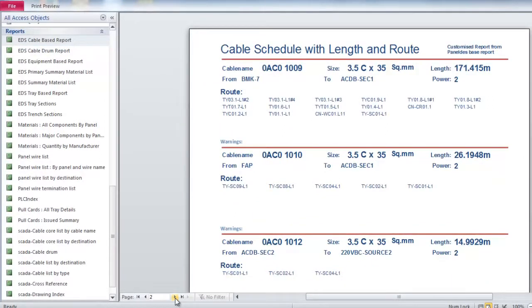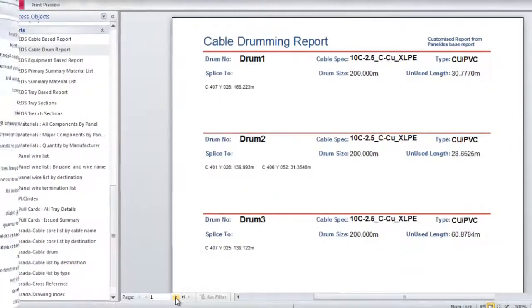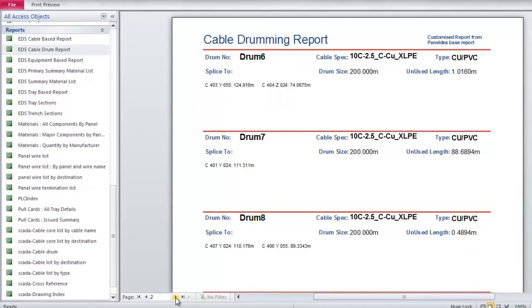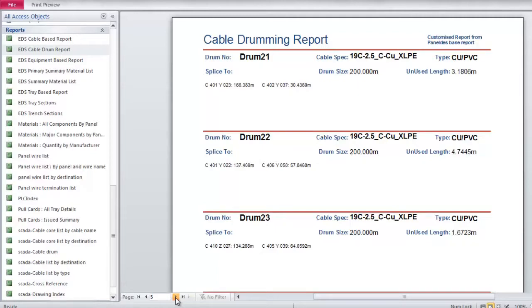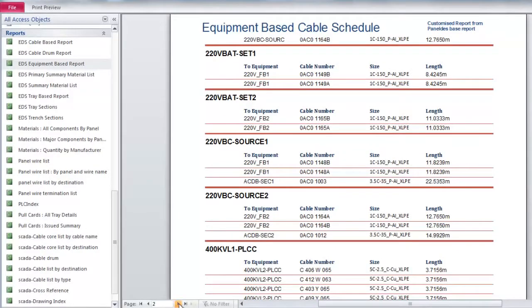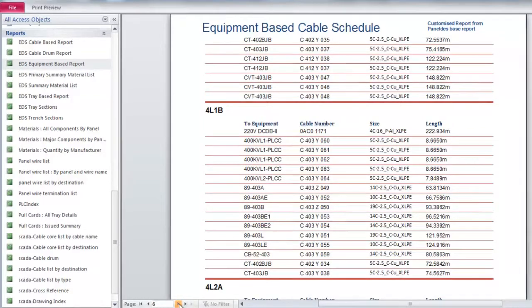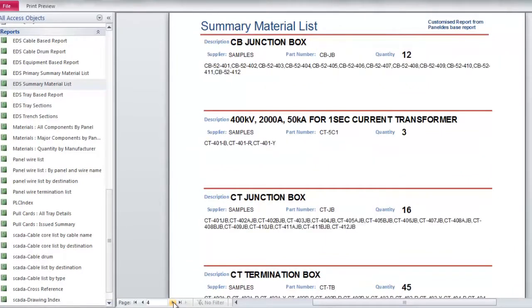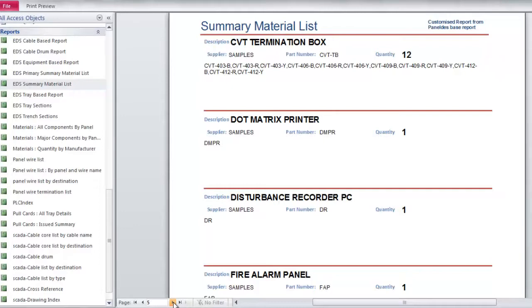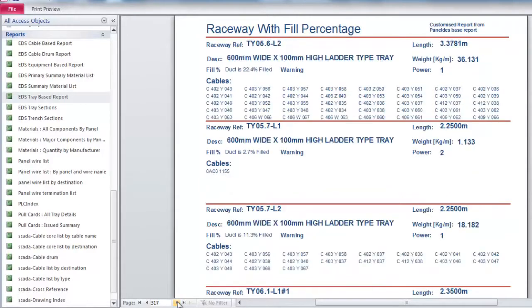PanelDes provides options for reports, including unformatted database data for importing to your own in-house systems such as SAP, as well as fully formatted reports where you can choose your own layout and content. The report database offers various pre-formatted reports, which can also be customized to user requirements, including material and cable lists, cross-section reports, cable reel reports, tray and conduit lists, as well as construction reports such as issued cable lists and pull cards.